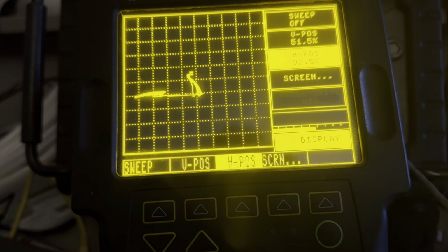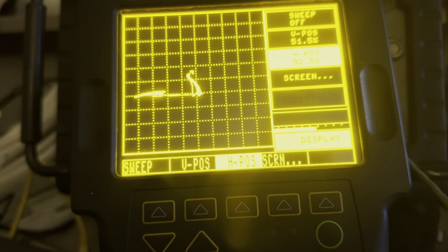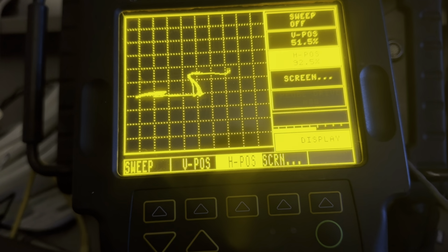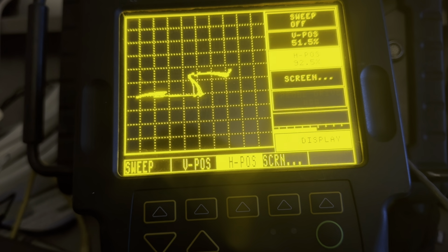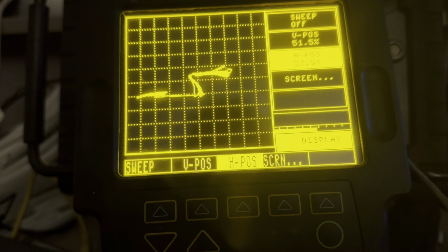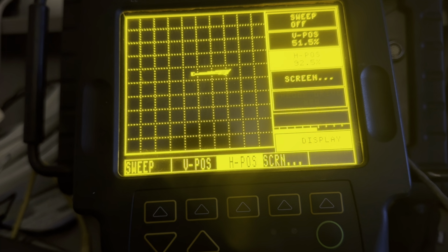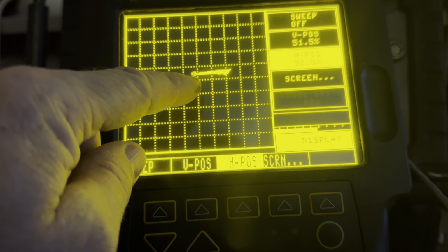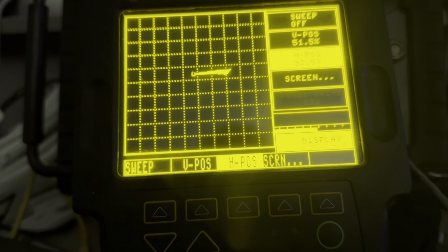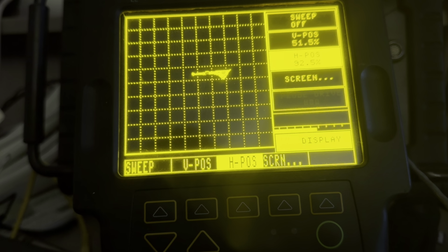Okay, so to prove that we can do some weld exams, I got a weld plate here somewhere. Right there. And I'm just going to set that down on the table here. Now, my EDM notch was aluminum, or my EDM block was aluminum, and this is carbon steel, or maybe some kind of stainless. Anyway, so the impedance trajectories are going to be a little bit different. There's unloaded, there's loaded, touching the material. So, keep in mind that differential arrangement probes are less prone to liftoff. See when my operating point is in air, where my coil's unloaded? Normally that shoots way off your screen, right? But because it's differential, there's just really not that much difference.